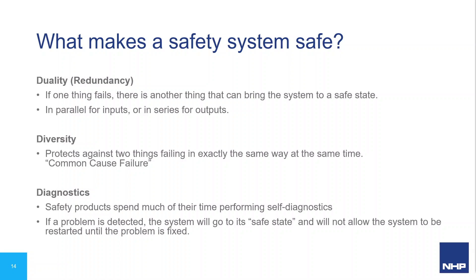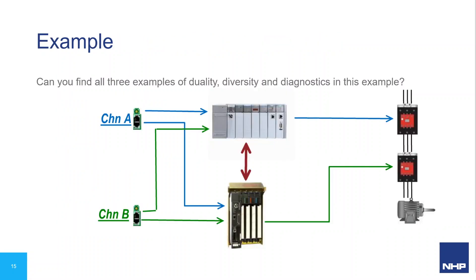And diagnostics: if a fault eventually occurs, we should be able to detect it, bring the machine to a safe state, and prevent restart until the fault is corrected. Here we have an example of a safety control system using standard components — two sensors monitoring a single guard, each fed into a logic controller (an SLC at the top and a PLC5 at the bottom), and two contactors controlling power to a motor. This example shows at least one instance each of duality, diversity, and diagnostics.